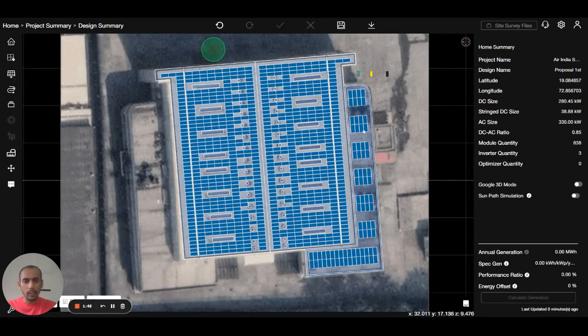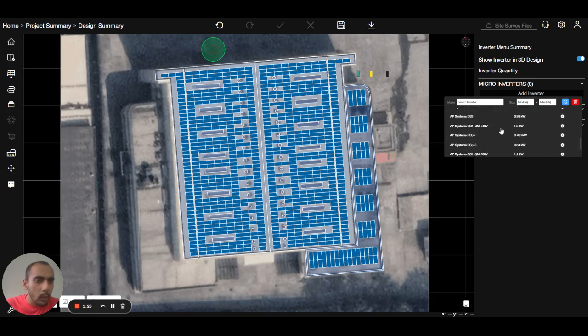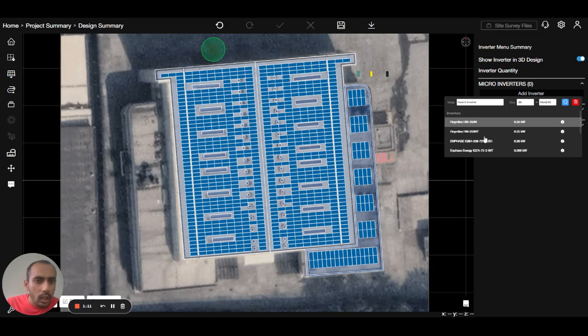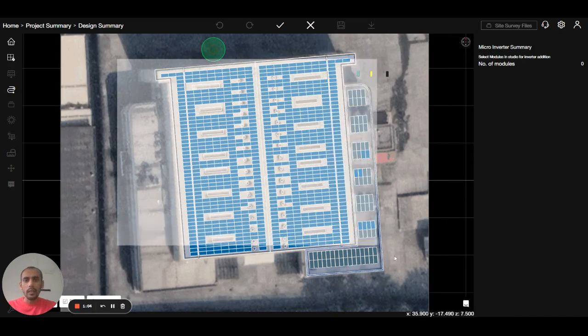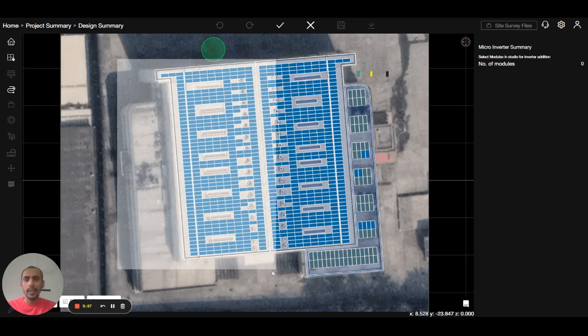Now let's look at how to place a micro inverter. Let's suppose I want to install a micro inverter here. Go to the component inverter menu, open the micro inverter, and add the inverter. Select the micro inverter you want to place — I will place a 0.35 kW unit because the panel is 550 W. I will make a rectangle over the area where I want to apply the micro inverter and select this inverter.